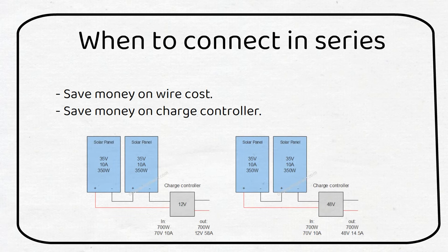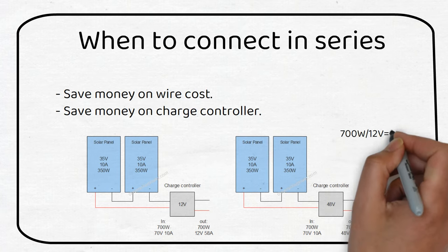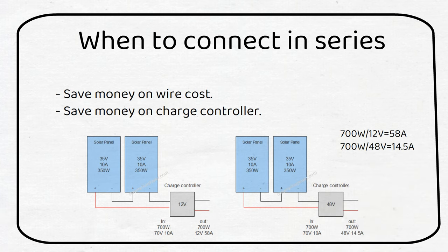Let's say you have an array of 700 watts and want to charge a 12 volt battery or a 48 volt battery. With a 12 volt battery you need a charge controller of 60 amps, while a 48 volt battery only needs a 15 amp charge controller.